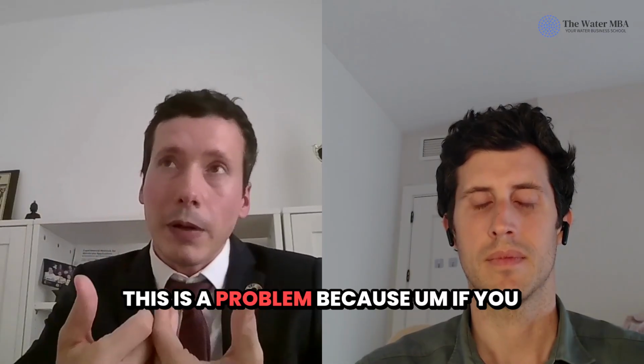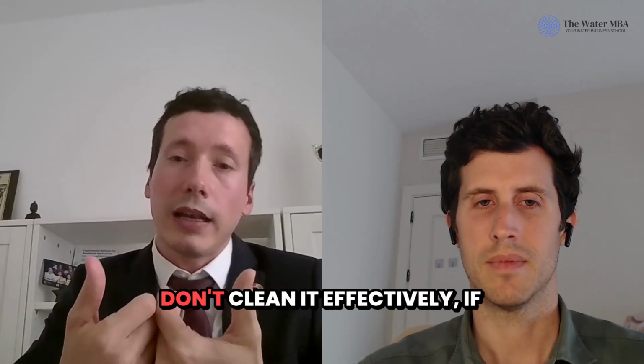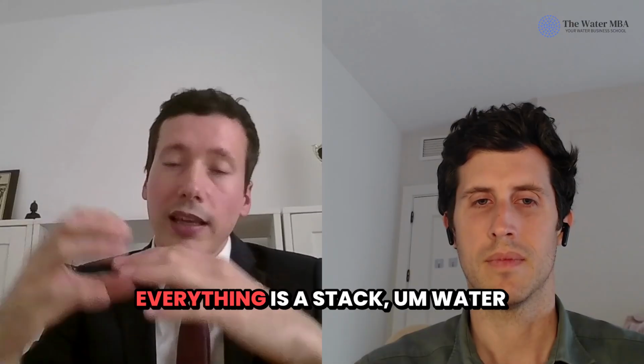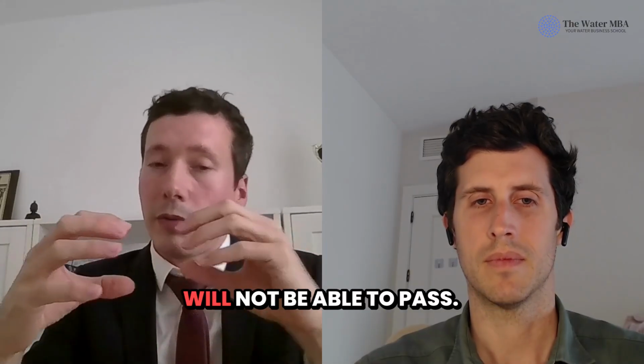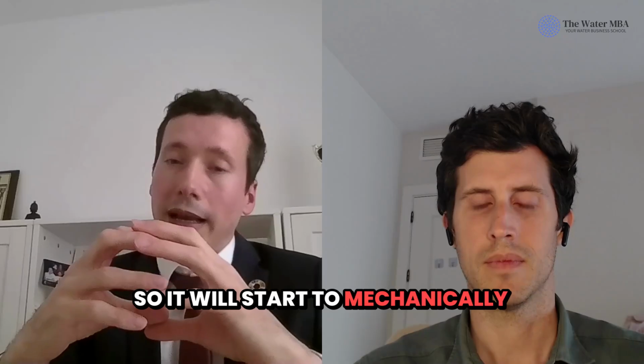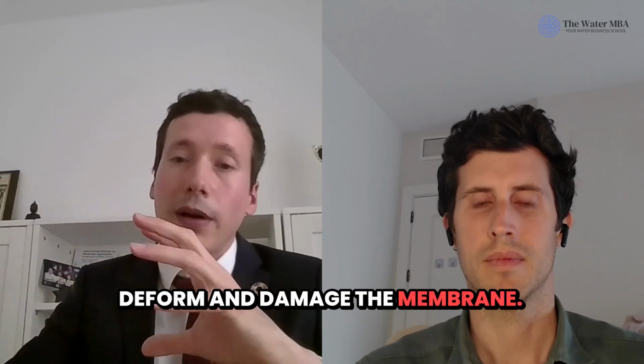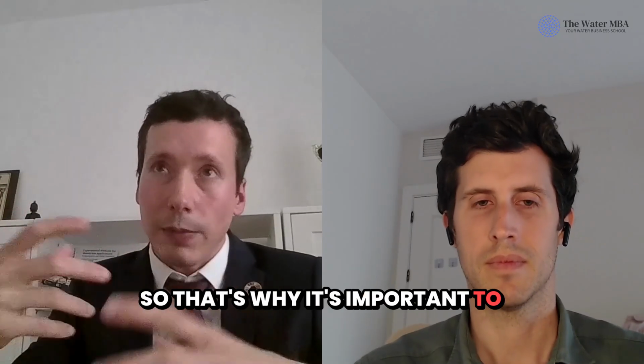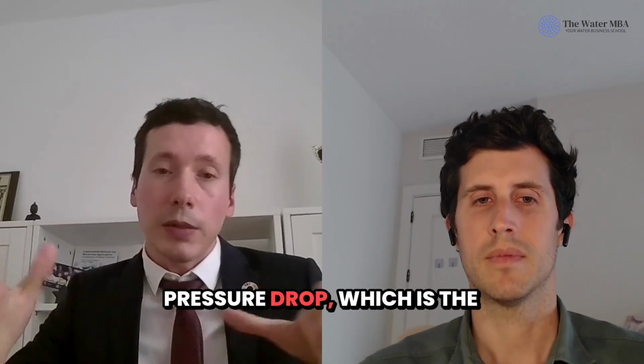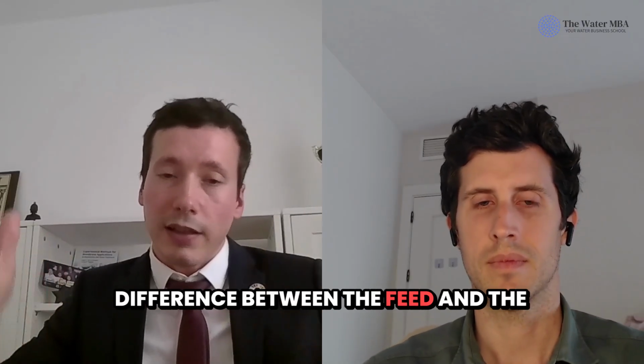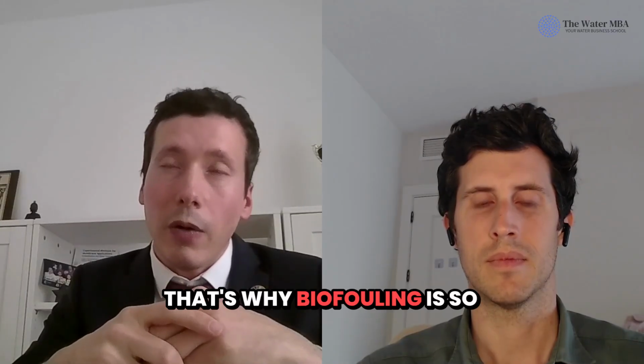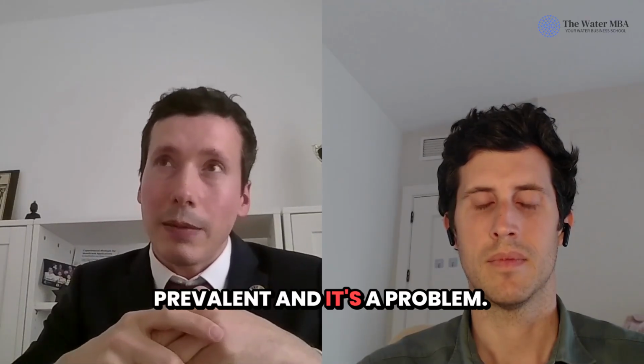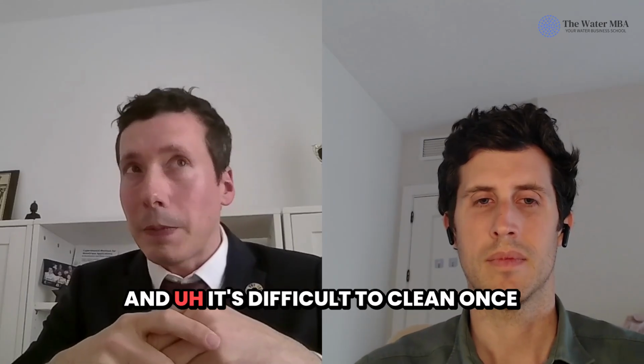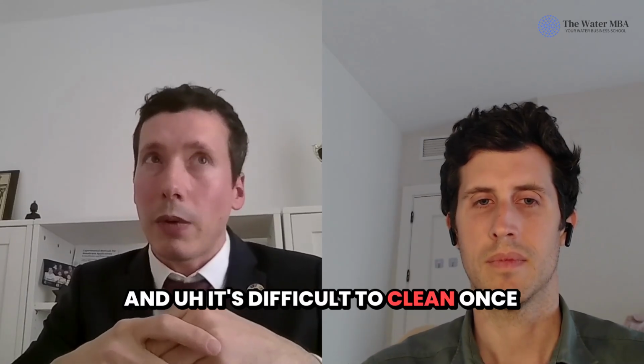And this is a problem because if you don't clean it effectively, if everything is stuck, water will not be able to pass, so it will start to mechanically deform, right, and damage the membrane. So that's why it's so important. Typically, you measure what we call pressure drop, which is the difference between the feed and the concentrate pressures. And that's why biofouling is so prevalent, and it's a problem. And it's difficult to clean once you have it.